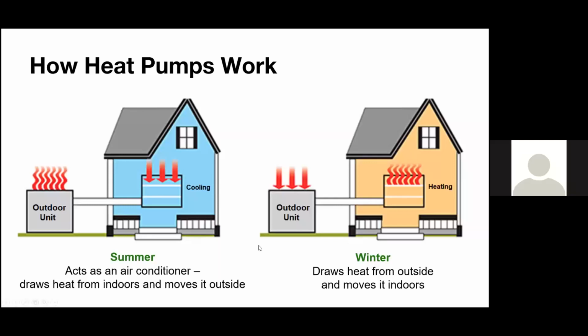So now we're air conditioning the outside. So if it's 50 degrees outside, but we're running refrigerant through it at 30 degrees and extracting heat from it, we start to cool that air. So eventually it's going to hit its dew point, and we're going to start to condensate water on the outdoor unit, which is fine. There are defensive designs for the water to fall off, but it's always important to think about where that condensate is located, because water is going to come out of the bottom of it. So that's not really an issue until it gets below freezing outside. So if it gets below 32 Fahrenheit, now you're condensating water on your outdoor coil, and that water is going to freeze, of course, when it's below freezing temperatures.